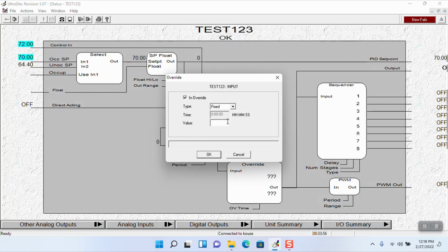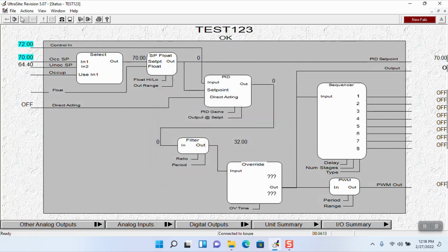I start out at 0.20, same thing with the I. I won't start at an I of 1, I'll start at an I of 0.5 or 0.20, and I'll slowly start increasing the P and the I. I'll start with the P till I get the graphs to stop. See if I can pull a graph here. Maybe I could show you guys kind of what it looks like.